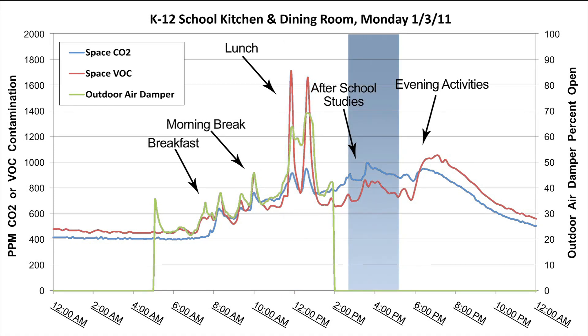Additional fresh air is brought in to dilute the VOCs during the lunch period. The outdoor air damper is closed at 2 p.m., but the room is still in use for after-school studies, so the VOCs and CO2 rise a little during this period from 2:30 to 5 p.m. Interestingly, there is a community meeting in the dining room at 6 p.m., and the audience is mostly adults. Notice how the VOCs track slightly below the CO2 during the after-school study period when it is mostly children in the room. Then the two switch, and the VOCs track slightly above the CO2 during the community meeting period when it is mostly adults in the room. That's because adults use more perfumes and colognes than kids, and therefore generate more VOCs than kids.